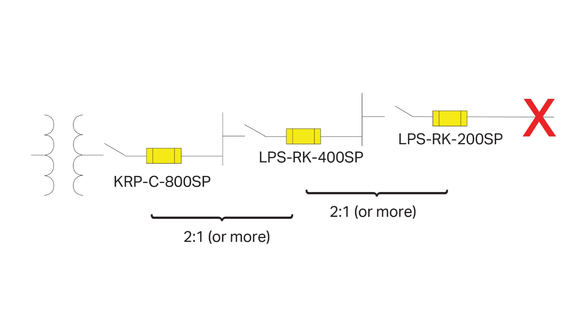Protecting electrical system components from fault currents is critical when selecting overcurrent protective devices. The engineer or specifier should consider the electrical circuit components' SCCR, such as wire, bus, or motor starters, and whether proper circuit protection will improve reliability and reduce the possibility of injury. Electrical systems can be destroyed if overcurrent protective devices do not limit the fault current to within the system's component short circuit current rating. Merely matching the component amp rating with the protective device amp rating does not ensure component protection under fault conditions.